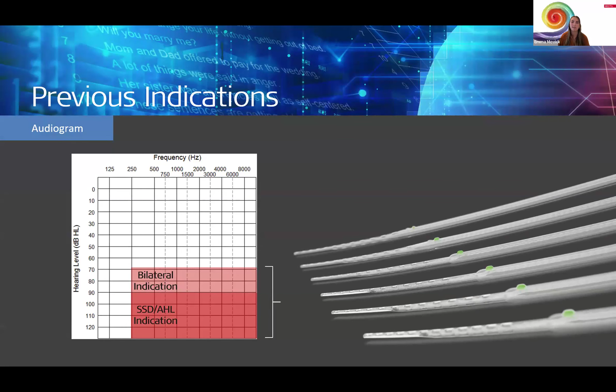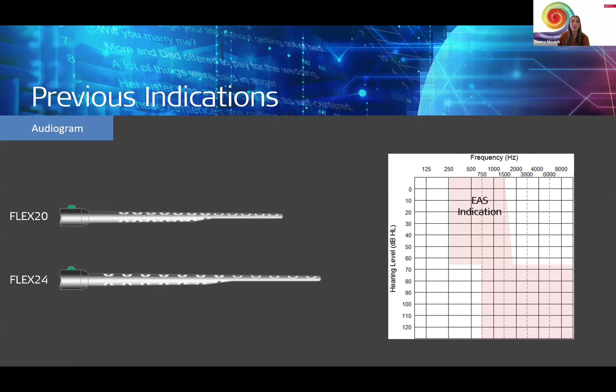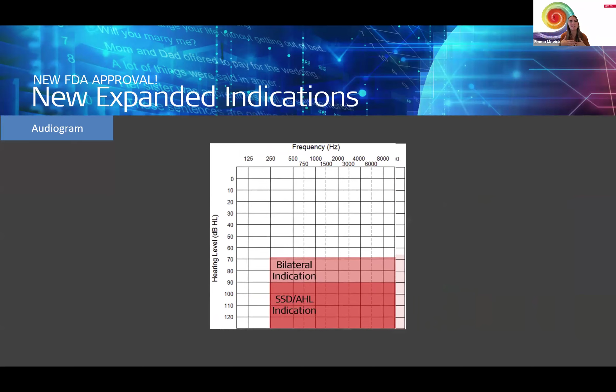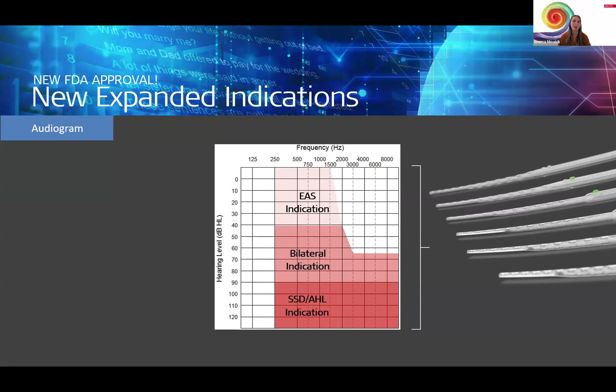We then had patients that had good low-frequency residual hearing, and so they would have an indication for EAS, which means that we're stimulating the high frequencies, but those low frequencies are still natural because that is where they have the residual hearing. Before, they were only approved to use either the Flex 20 or the Flex 24, which are the shortest of the electrode array portfolio, so that it would give that high-frequency information, but not get into the range of the low frequencies. But with our expanded indications, we get to have this fun combination of the two, so we can overlap those two audiograms as well as offer any length of electrode array. And we're ensuring that that will give that hearing preservation in the low frequencies. So patients with low-frequency hearing can still benefit from a longer electrode array.